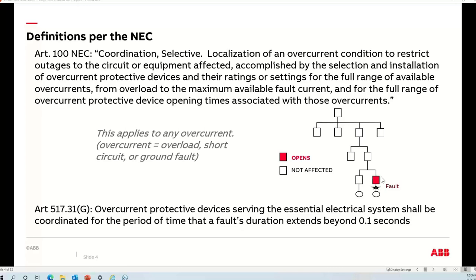As the polling question showed, there are still some interpretation differences. I feel those come about from the fact that the term 'overcurrent' may not be explicitly defined in the NEC, though it is defined in IEEE literature. For the 80% that voted that the definition applies to overloads, short circuit, and ground fault, you're using the same definition I would. This is the assumption I'm working under today — when we're talking about selective coordination, we're talking about any possible type of fault current out to the maximum available fault current.